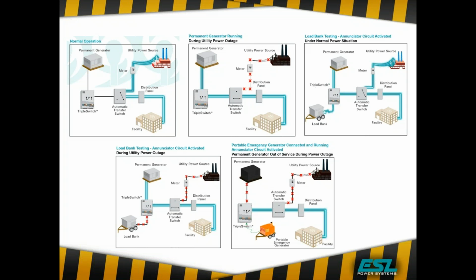It's a unique product, and what it does is allow you to provide solutions without having to design in a lot of extra breakers, a lot of Kirk locks, and it's really a drop-in solution, especially as you're asked by your clients to retrofit existing generators. They want to meet 2017 700.3F, or they want to start load bank testing their permanent generators because they've had issues in the past. The triple switch provides a very user-friendly, very unique drop-in solution for you to provide them.